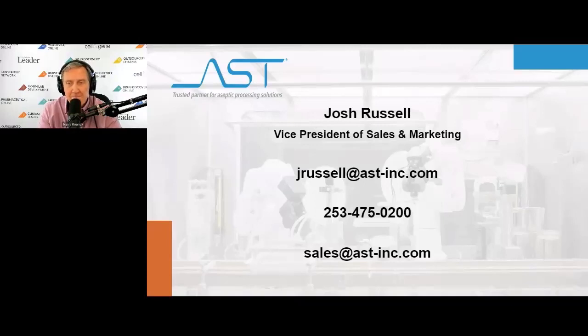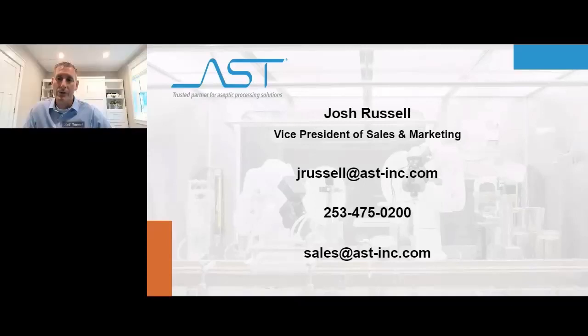Yeah, so a couple typical things that our customers would do with an isolator-based platform is, one, between batches, there's an automated biodecontamination process using the onboard hydrogen peroxide system that will biodecontaminate the interior using hydrogen peroxide. Then another approach is we commonly use single-use technologies and single-use fluid paths, and that's really what we demonstrated. Anything that's directly product contacting is removed and disposed, and then new single-use fluid paths are put in place. That eliminates a lot of the clean in place, and product carryover from one batch to the next is truly eliminated.